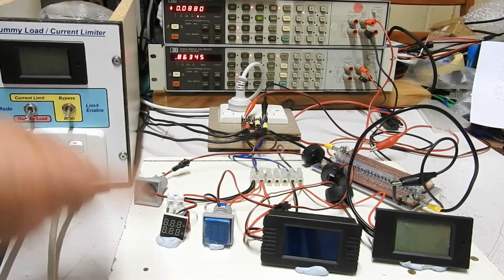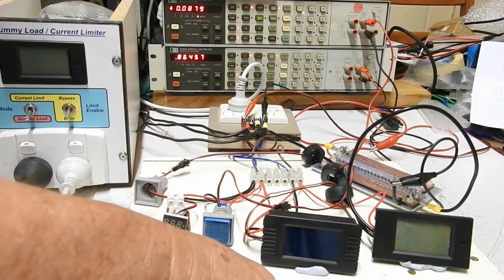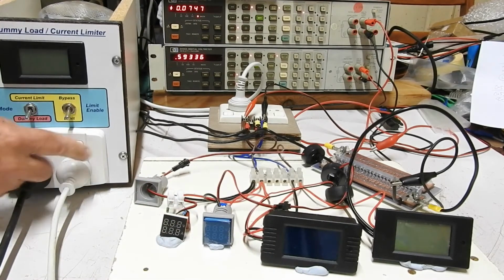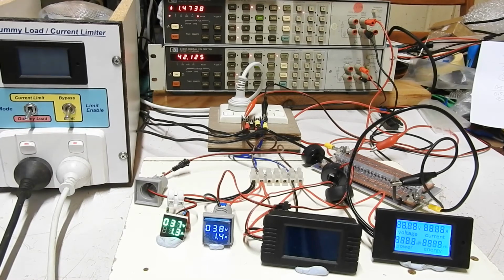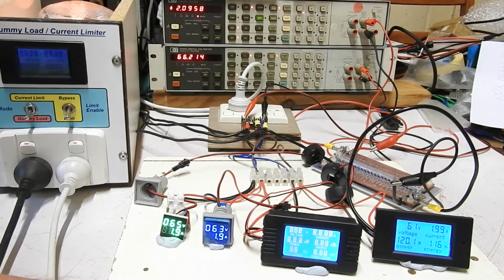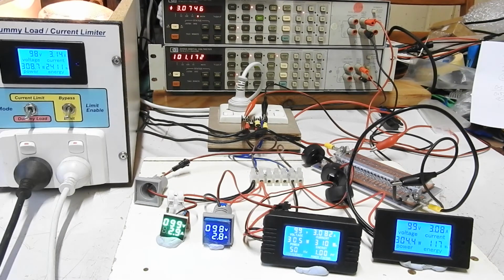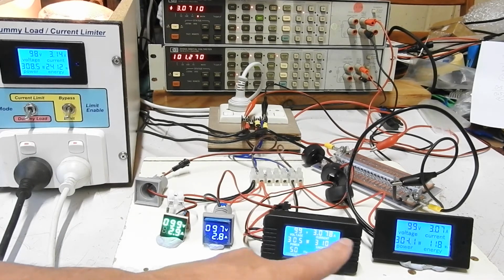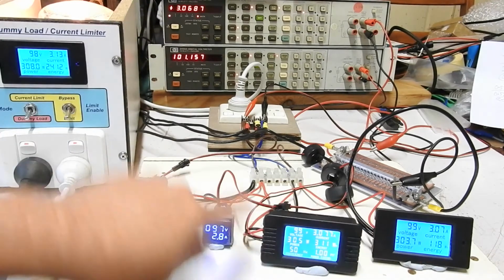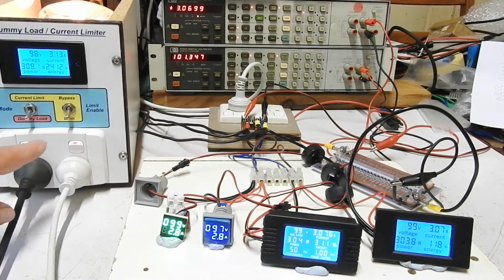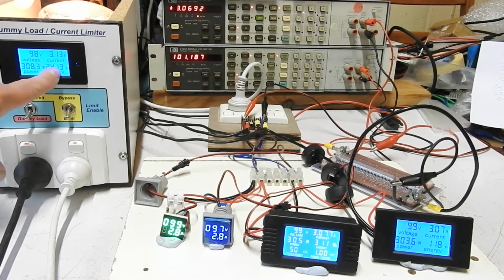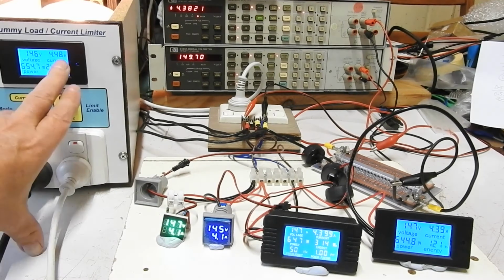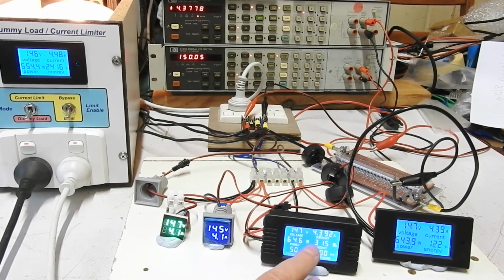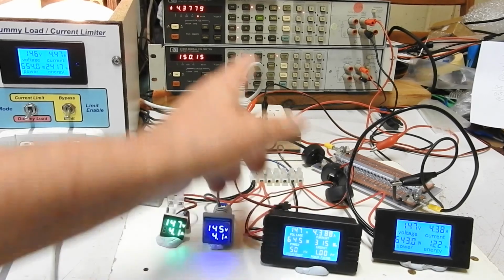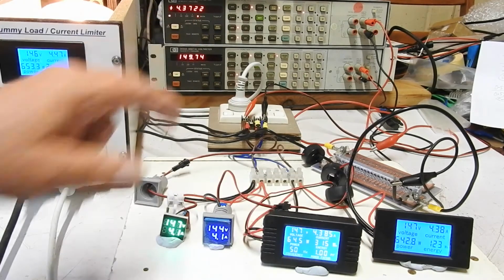Okay, winding up, and I've got the toaster oven down there and the space heater both turned on and switched in, plus the bulbs, so winding up the voltage. Let's take it to 100 odd volts, 3.14 amps. These are reading low, 3.077, 3.07. So these two are in pretty good agreement with the HP at the top there. This one here is reading a bit high, 150 volts, 4.48 still high, 4.39, 4.37, 4.38. So these two are in pretty good agreement with the top meter.